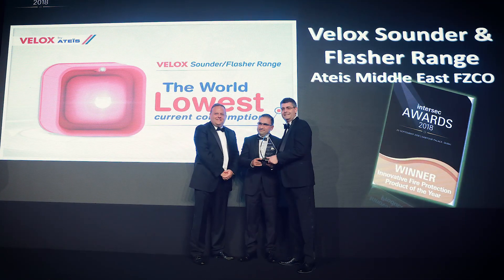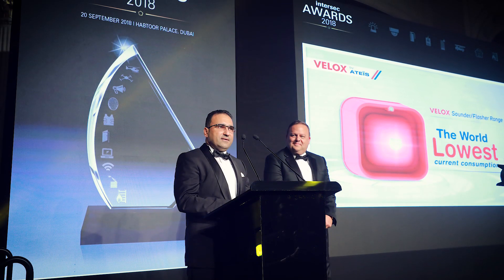Ateis Middle East actually won an Intersec award for a product developed here in Dubai — a patented micropower technology on our sounder and sounder flasher. We re-innovated how sounders behave in fire alarm systems, harnessing around 80% of previously wasted energy back to the device, lowering current and power consumption, and allowing more than 200 devices to connect on a single loop. It's the first UAE patent in fire detection and alarm systems.